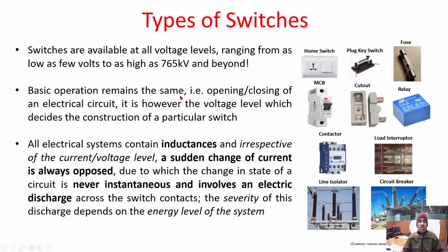That's what I said, not only voltage but also current. Therefore, the power level or energy level decides it. The storage elements such as inductances and capacitances involved in the system also influence it. Basically, sudden interruption of current is not allowed by an inductance. Therefore, energy gets redistributed, and there will be an associated transient.